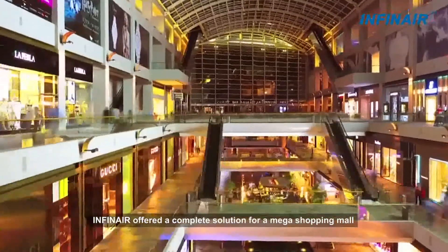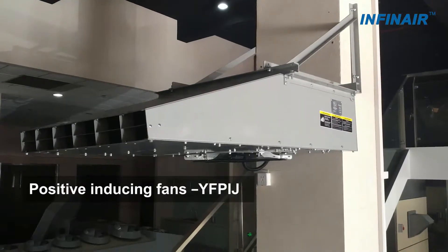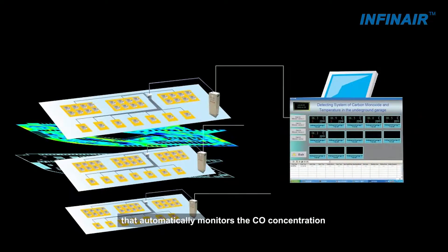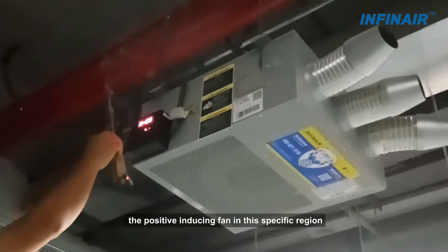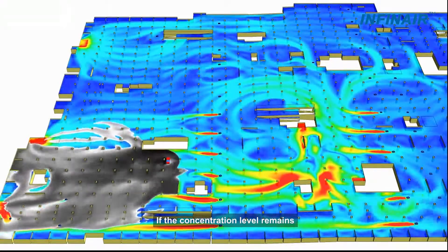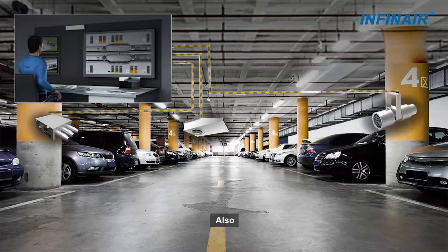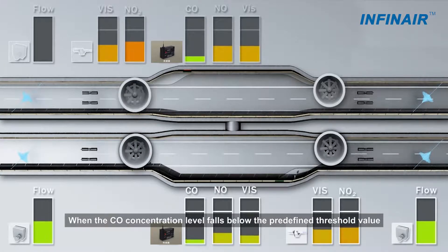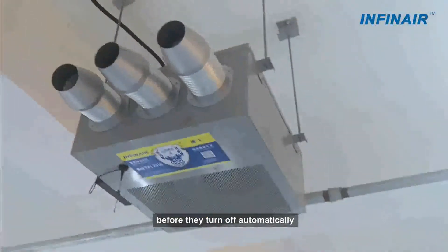For example, INFINAIR offered a complete solution for a mega shopping mall, involving underground six-story car park ventilation design, positive-inducing fans YFP-IJ, inline vane axial fan YF-IM, control cabinets, and an intelligent system that automatically monitors carbon monoxide concentration. Upon detection of excessive carbon monoxide, the positive-inducing fan in the specific region will start automatically and run for five minutes. If the concentration level remains, all intelligent positive-inducing fans in the interlinked sub-regions will be initiated, and supply and exhaust fans will begin to remove air pollutants and bring in fresh air. When the concentration falls below the predefined threshold, the fans continue to run for another ten minutes before turning off automatically.